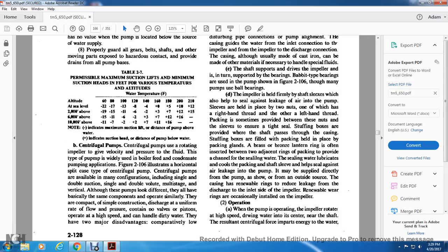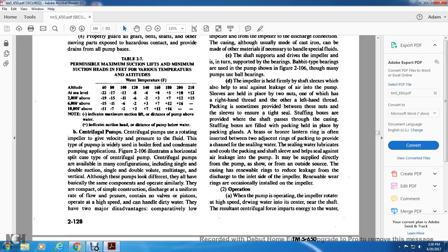Stuffing boxes are filled with packing held in place by packing glands. A brass or bronze lantern ring is often inserted between two adjacent rings of the packing to provide a channel for the sealing water. The sealing water lubricates and cools the packing. The shaft sleeve helps to seal against leakage into the pump. The sealing water may be supplied directly from the pump or from an outside source. Renewable wear rings in the casing reduce leakage from the discharge to the inlet side of the impeller, and are occasionally installed on the impeller too.